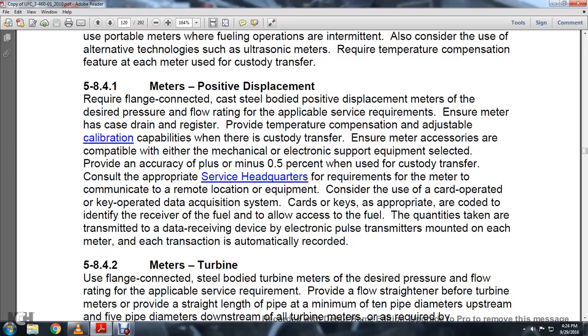5.8.4.1 meters, positive displacement. Require flange-connected, cast steel body positive displacement meters sized for the desired pressure, flow rating, and applicable service requirement. Ensure the meter has a drain register. Provide temperature compensation and adjustable calibration capabilities where there is a custody transfer. Ensure the meter accessories are compatible with whichever mechanical or electronic support equipment is selected. Provide an accuracy of plus or minus 0.5% when used for custody transfer. Consult the appropriate service headquarters manual for the requirements of the meter communication and remote location equipment. Consider the use of a card-operated or key-operated data acquisition system.